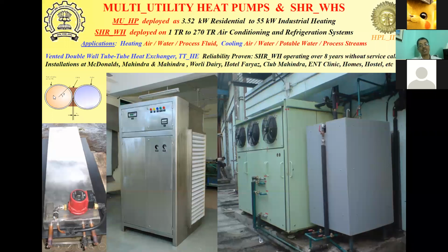And in this case, one fluid passes in one of the tubes and the other fluid passes through the second tube. The advantage of this heat exchanger is that you can select the material of construction of the 2 tubes independent of each other. If I were to give you an example of seawater being cooled using ammonia, the only common material that is available is titanium, which becomes very costly, which is compatible both with seawater and ammonia. But in the tube-tube configuration, we can use cupronickel for seawater, and the ammonia tube can be carbon steel, stainless steel, any of these metallurgies, which is much cheaper than your titanium tube. Titanium, of course, is also difficult to work with, and these common materials of construction will be much cheaper in this.